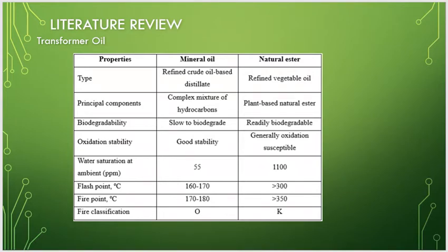For oxidation stability, mineral oil has good stability, and natural ester is generally susceptible to oxidation. For water saturation at ambient temperature, mineral oil is 55 ppm, and natural ester is 1100 ppm. For flash point, mineral oil is 160 to 170, and natural ester is more than 300 degrees Celsius. The fire point for mineral oil is 170 to 180, and for natural ester is more than 350. The fire classification for mineral oil is O, and for natural ester is K.